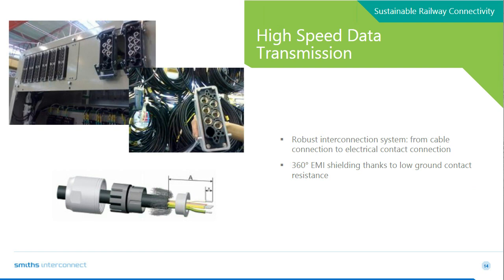Typically, to reduce maintenance and electrical failures, one solution is to design a robust interconnection system from cable connection to electrical contact connection. For that, cable fixing is mandatory, and it can be achieved through a robust cable clamp system that connects efficiently the cable shielding braid. A good EMC connection is achieved with a shielding braid connection over 360 degrees, as you can see in the picture on the left, below.